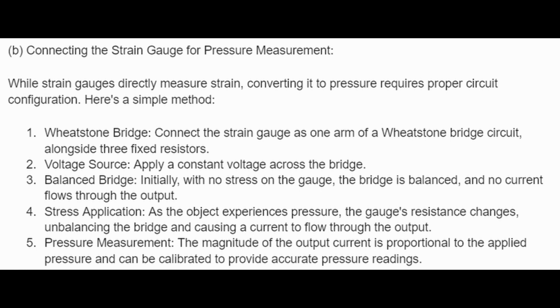B. Connecting the strain gauge for pressure measurement. While strain gauges directly measure strain, converting it to pressure requires proper circuit configuration. Here's a simple method. 1. Use a Wheatstone bridge. Connect the strain gauge as one arm of a Wheatstone bridge circuit alongside 3 fixed resistors. 2. Voltage source. Apply a constant voltage across the bridge.